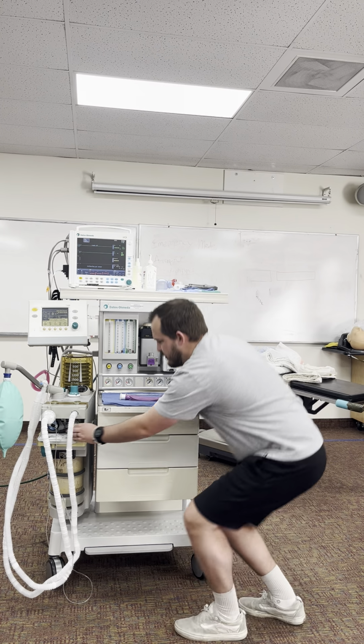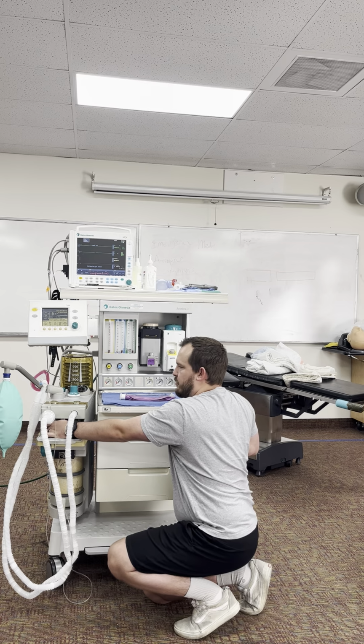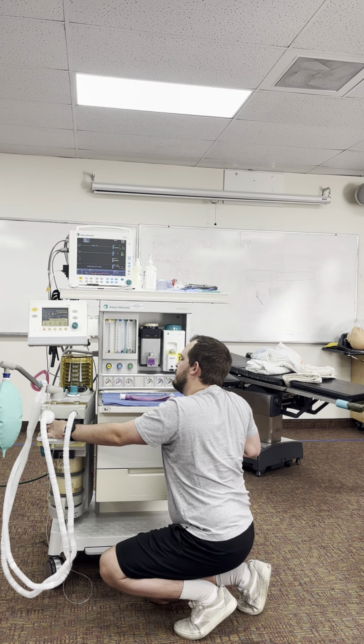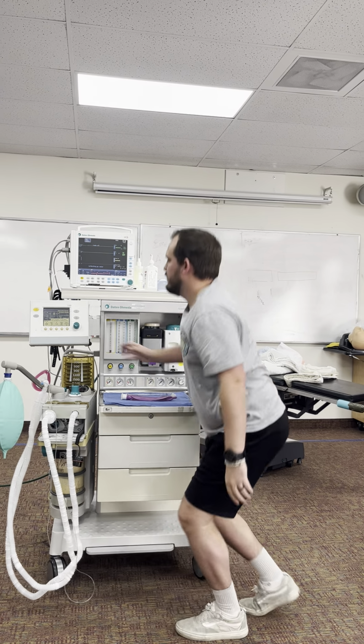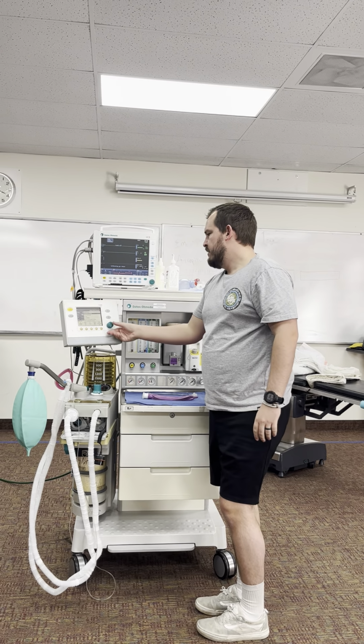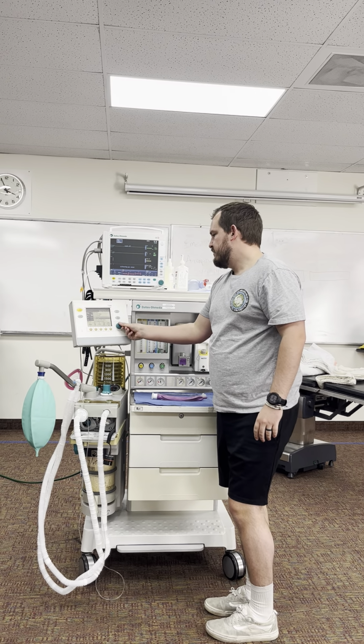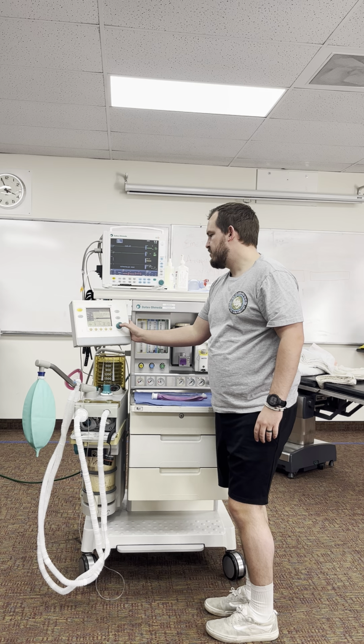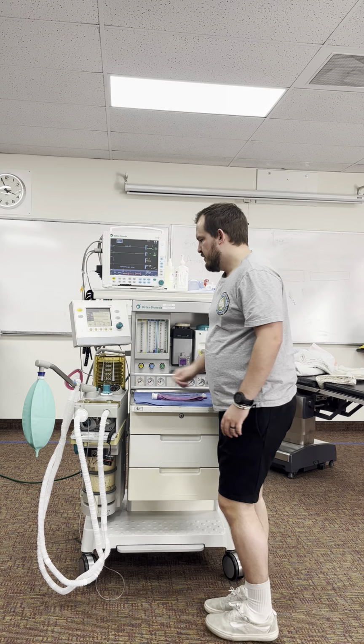Now I'm going to calibrate my machine. I'm going to open up here and take out the O2 caliber plug. Leave that open. I'm going to hit my ventilator. Go to calibration, O2 sensor, 21%. We're going to let it calibrate.